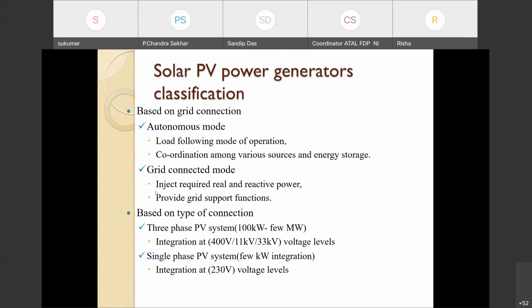However, because we have the current injection and we can vary the current injection, it is unlike the load following mode of operation. We can go for grid supportive functions derived from the solar panel output. We can go for different current production according to the frequency and according to the voltage so that we'll be able to generate the grid providing support.